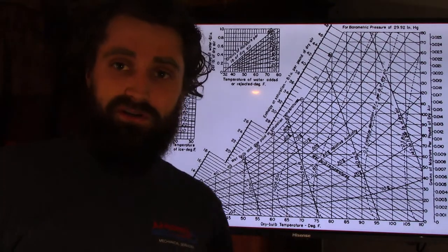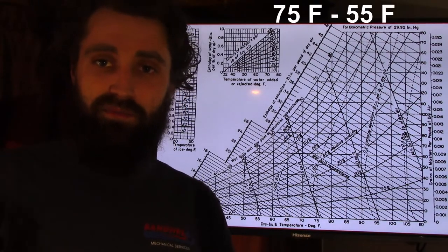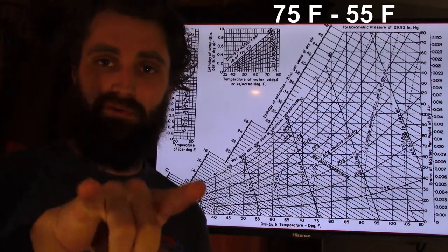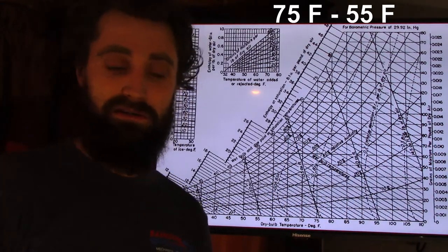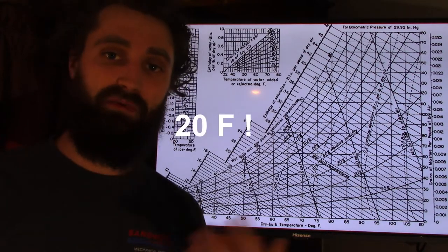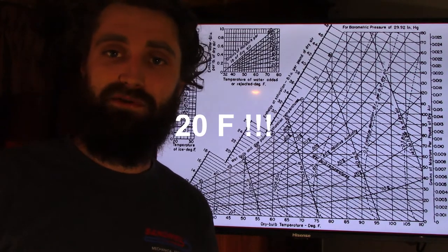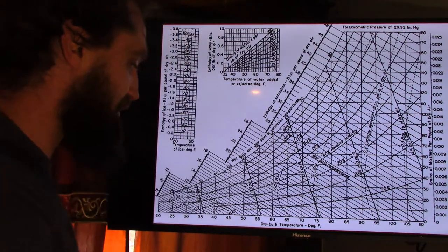Now, if you're just taking your temperature probes and sticking them supply and return, or before and after the evaporator coil, you're seeing a 20 degree drop. You might just write that thing off as good. Yeah, I'm getting a 20 degree drop. It's August. I can't ask for anything more. That thing's doing great. But let's take another look here.